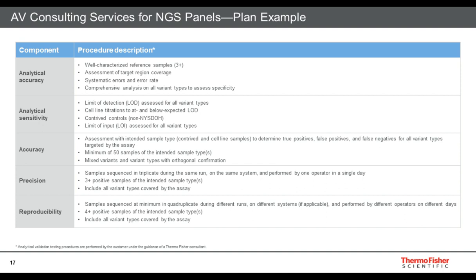We then segue into accuracy — running the meat of the validation with your intended sample type. We also use contrived controls and cell lines mainly to build up the number of variants, since fusion events are very rare in real samples. We take a contrived control and run it to build up the number of fusions the assay is designed to detect. Next is precision — intra-assay repeatability. If we take one sample and repeat it in triplicate on the same system, by the same operator, on the same day, do we get the same variant results, covering all variant types covered by the assay?